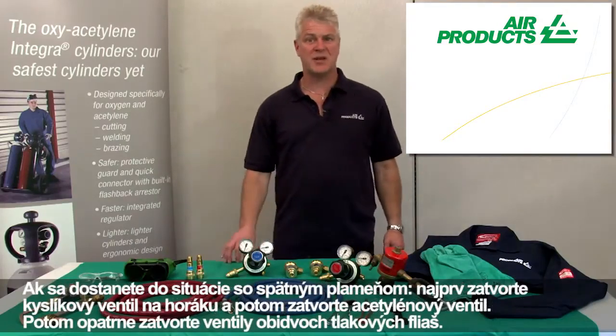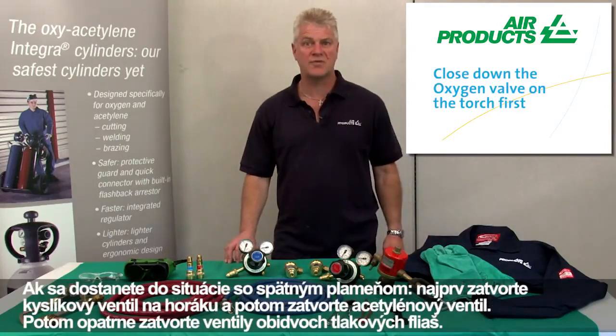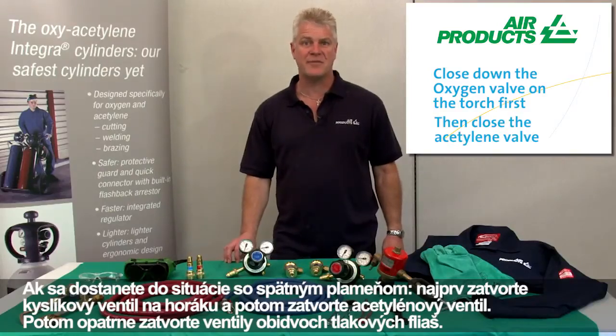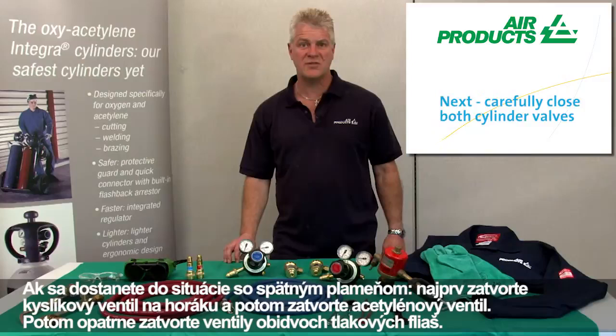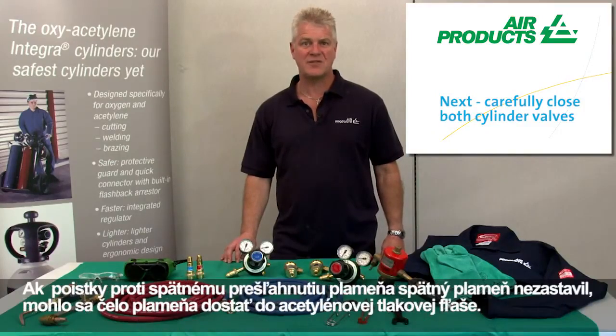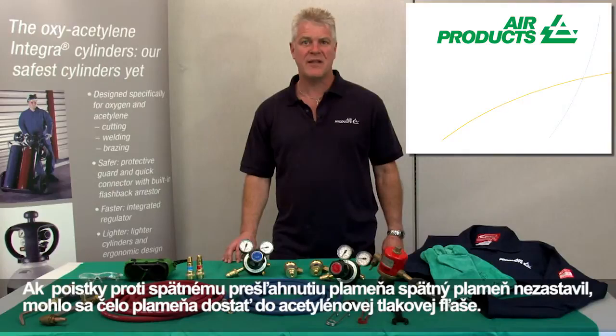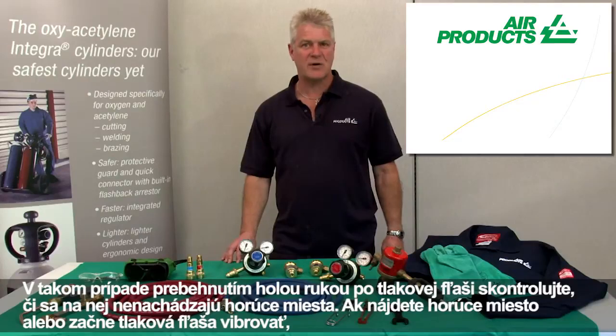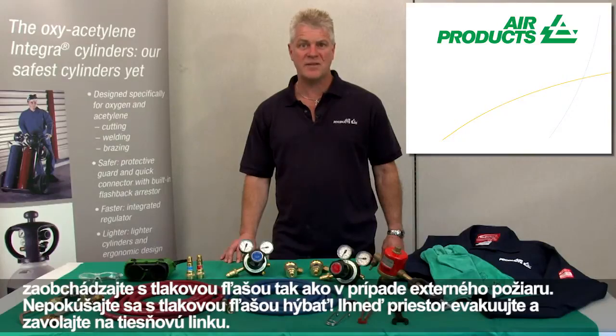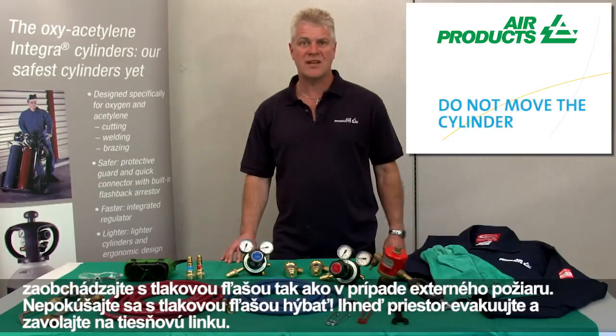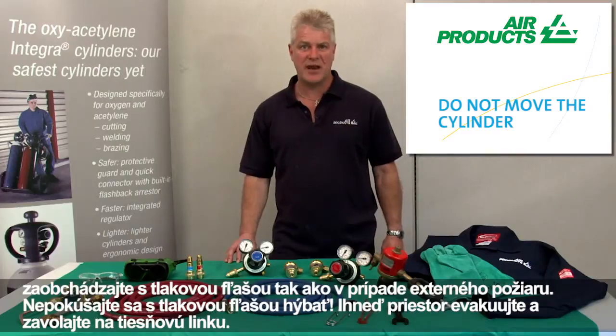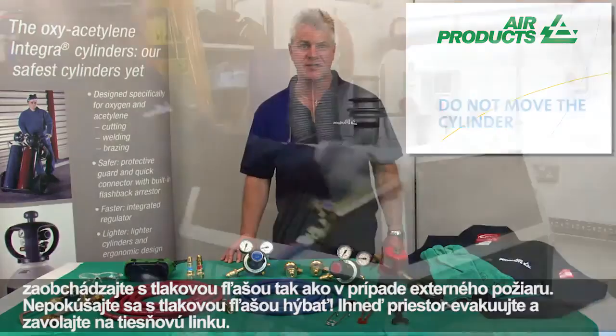If you get a flashback situation, close down the oxygen valve on the torch first, then close the acetylene valve. Next, carefully close both cylinder valves. If the flashback arrestor didn't stop the flashback, then the flame front may have entered the acetylene cylinder. Now check the cylinder for hot spots by running a bare hand over its surface. If a hotspot's detected or the cylinder begins to vibrate, treat it as if it's been involved in an external fire. Do not attempt to move the cylinder. Evacuate the area immediately and call the emergency services.